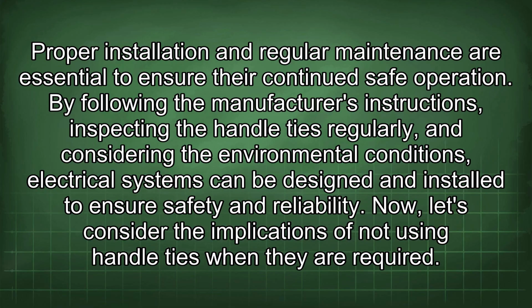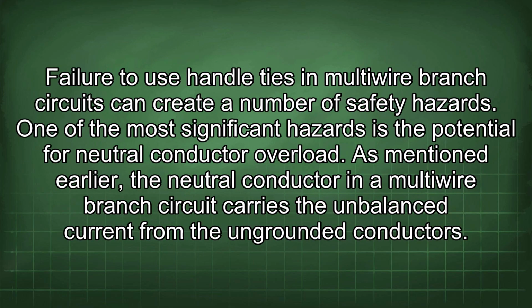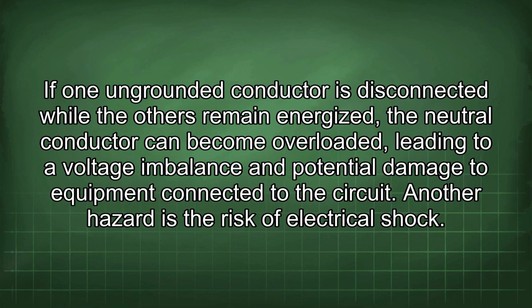Now, let's consider the implications of not using handle ties when they are required. Failure to use handle ties in multi-wire branch circuits can create a number of safety hazards. One of the most significant hazards is the potential for neutral conductor overload. As mentioned earlier, the neutral conductor in a multi-wire branch circuit carries the unbalanced current from the ungrounded conductors. If one ungrounded conductor is disconnected while the others remain energized, the neutral conductor can become overloaded, leading to a voltage imbalance and potential damage to equipment connected to the circuit.